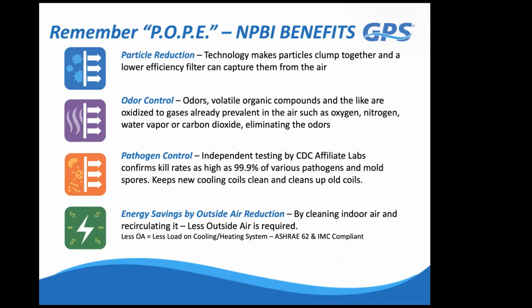Just remember the acronym POPE again: particle reduction through agglomeration. We make the particles bigger, which makes the air handlers more efficient at capturing them. We break down the gases and odors through oxidation. So don't be confused with how the system works between particles and odors. With gases, we don't physically make them stick together and go back to the air handler to the filters like the particles. We physically rip them apart in the space and break them down. So we're not relying on filters to take the particles or the gases out of the air.